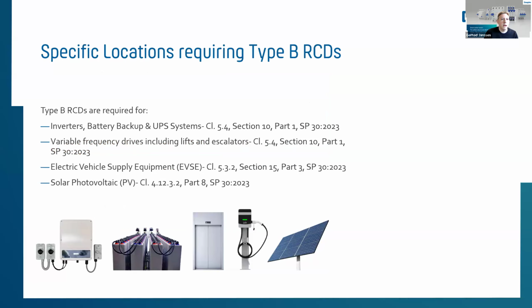So inverters, battery backup systems, UPS systems, also, as per your national standard code, VFD drives, escalators, lift applications, crane installations with big motors driven by VFDs, and also the whole big story of electrical vehicles. Supply for electrical vehicles often requires a type B RCCB to be protected against direct DC currents, which can arise from those charging points. Solar photovoltaic systems are meanwhile an application growing in a lot of markets, but very often installed without the proper protection, which in the best cases is the type B RCCB.